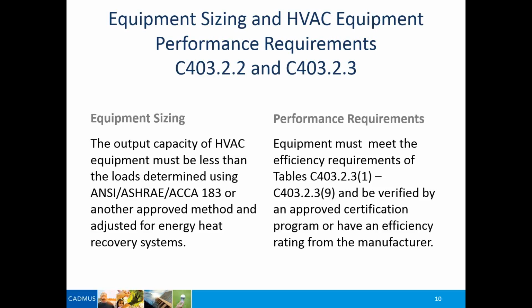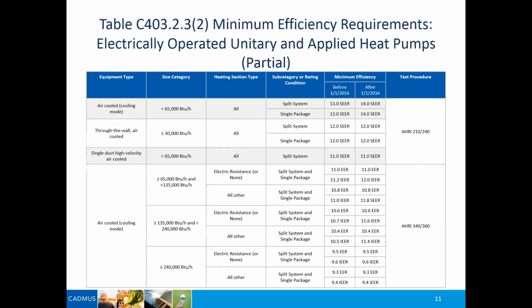So the equipment sizing requirement basically now requires either ASHRAE or ANSI/ASHRAE/ACCA 183 or another approved equivalent method to size your cooling systems so that it actually is sized for the building. And then you need to make sure that you actually select a piece of equipment that meets the efficiency requirements, the current efficiency requirements that are in the code. And so these tables have been updated. The minimum efficiency requirements have been updated.